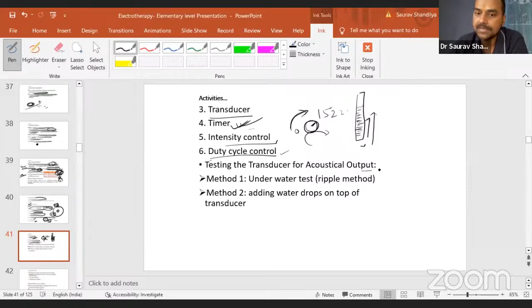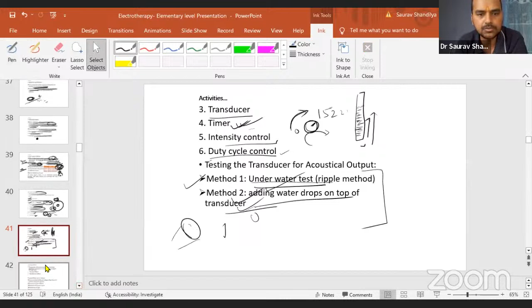Now, duty cycle control, always check whether duty cycle control is working. Now, testing method is very, very important. I don't know, all of you must be testing the ultrasound with method 1, where we take the head of the transducer, and after that we put drops of water here, and then when we start the intensity, the drops start vibrating. That's the wonderful test. Okay, sorry, method 2, most of us are testing by adding water drops on top of the transducer, but there is also an underwater test, the ripple method, you can try that as well. It's good to check that method also.